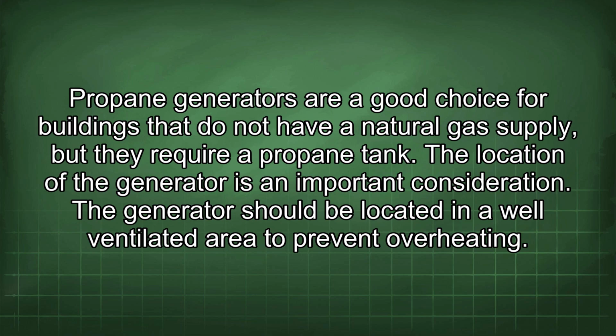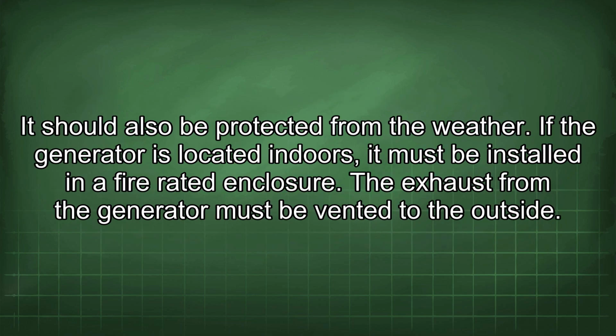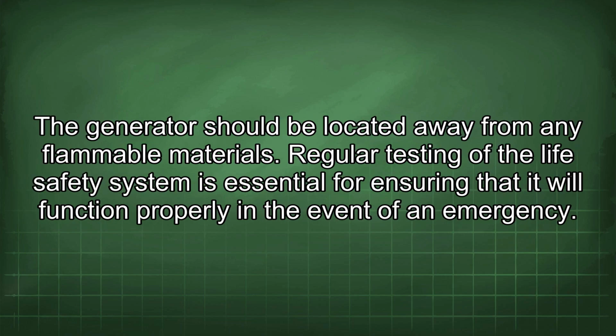The generator should be located in a well-ventilated area to prevent overheating. It should also be protected from the weather. If the generator is located indoors, it must be installed in a fire-rated enclosure. The exhaust from the generator must be vented to the outside. The generator should be located away from any flammable materials.